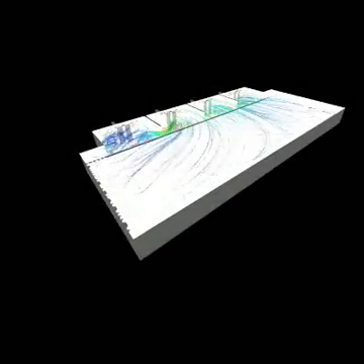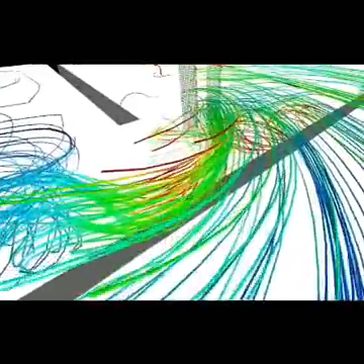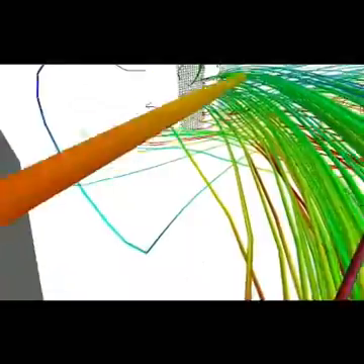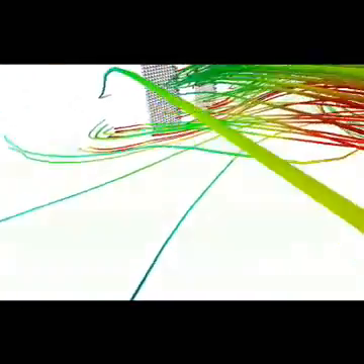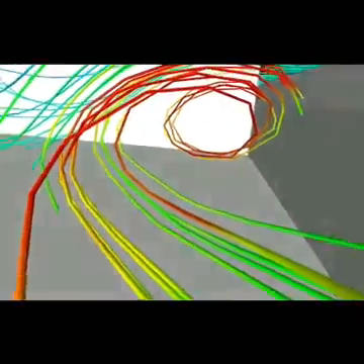Two new cooling towers at BP have been designed to remove heat from a refinery. As we see here, this basin is filled with water. If we fly into the flow, then we can see the flow pattern at the bottom of the basin. Due to the change of geometry at the floor, there is circulation at the bottom.